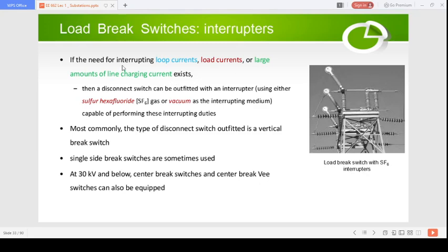If you need to interrupt the loop current, load current, or a large amount of line charging current, then the disconnect switch can be outfitted with an interrupter, as shown in here. This interrupter can use either sulfur hexafluoride or SF6 gas, or vacuum, as an interrupting medium. So this is then capable of performing interruption for high currents like load current or a large amount of line charging current.